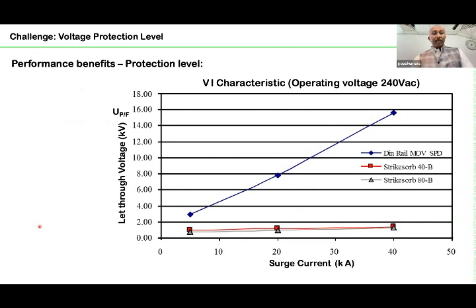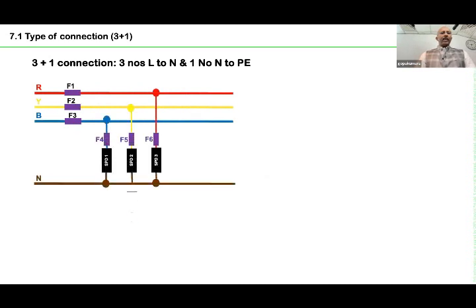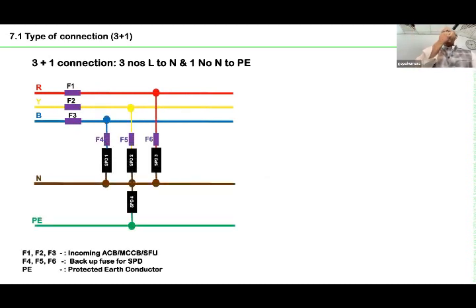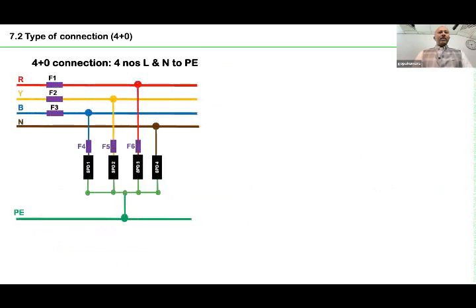Also, one more important subject is, if you are going for a 4+0 connection, one moment. I've shown some of the connections, 3+1, 4+0. So this is called a 3+1 connection. Means from the line to neutral, 3 SPDs, and from the neutral to earth, 1 SPD. And this is called 4+0. That means from all the 4 current-carrying conductors, there is an SPD to the earth. Now, as I said, at the mains incoming, the best way is to go for the 4+0 connection.